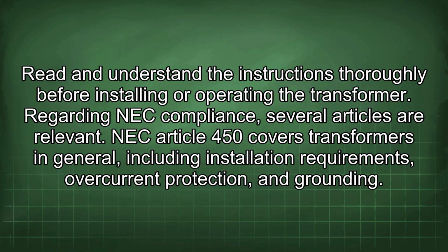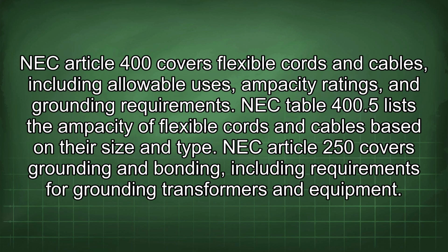Regarding NEC compliance, several articles are relevant. NEC Article 450 covers transformers in general, including installation requirements, overcurrent protection, and grounding. NEC Article 400 covers flexible cords and cables, including allowable uses, ampacity ratings, and grounding requirements. NEC Table 400.5 lists the ampacity of flexible cords and cables based on their size and type. NEC Article 250 covers grounding and bonding, including requirements for grounding transformers and equipment.